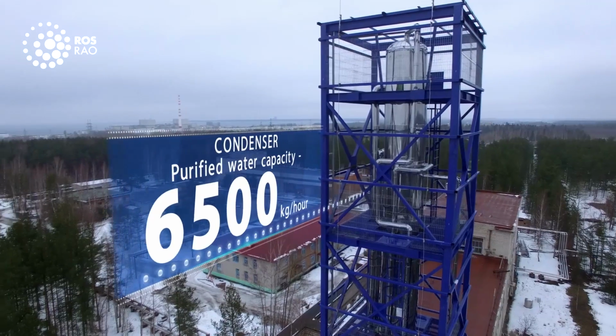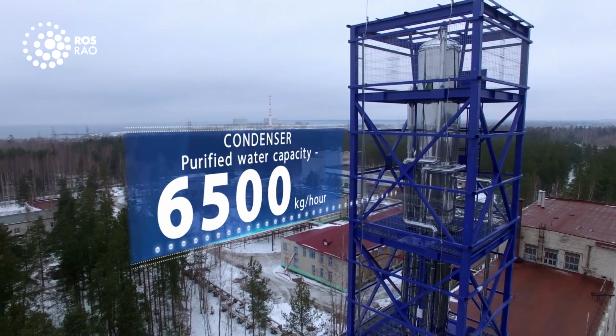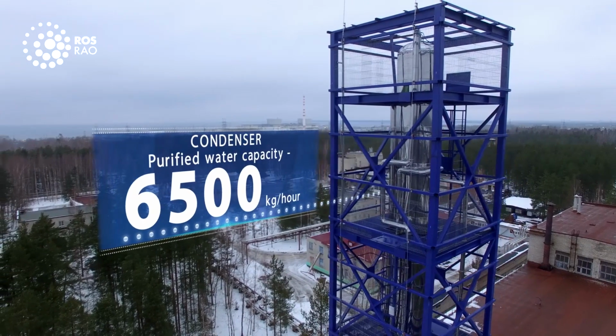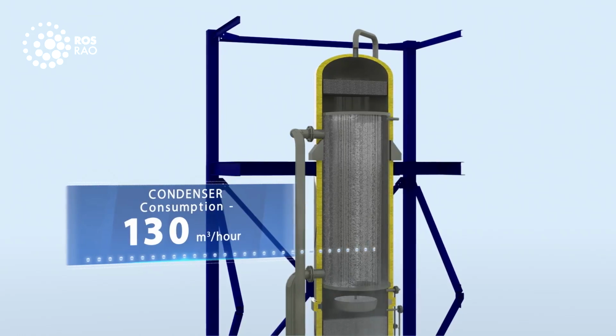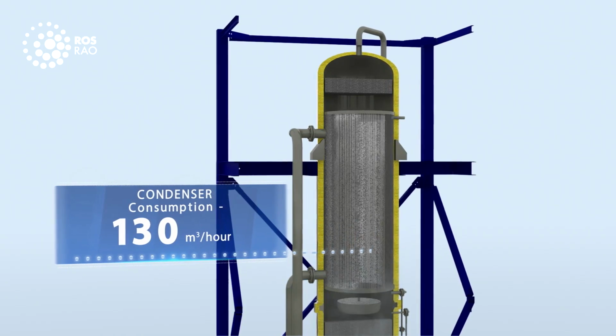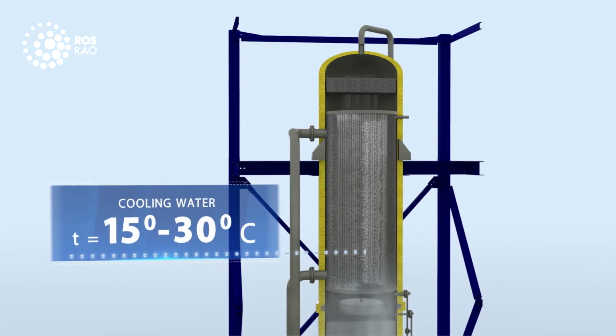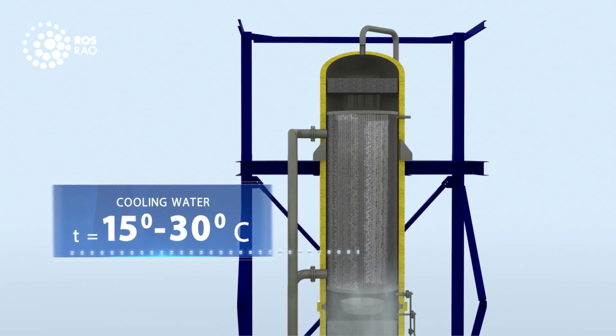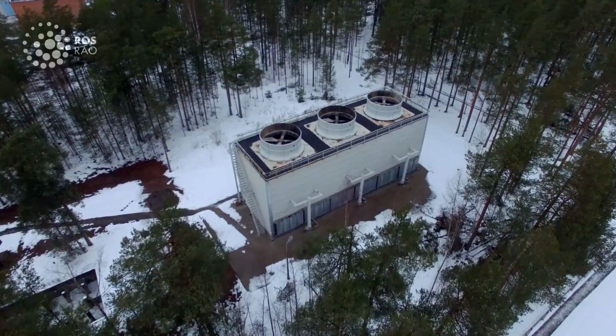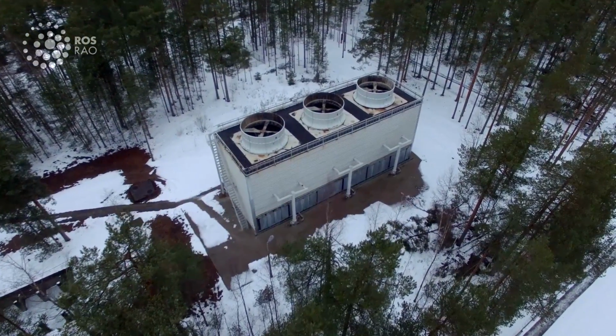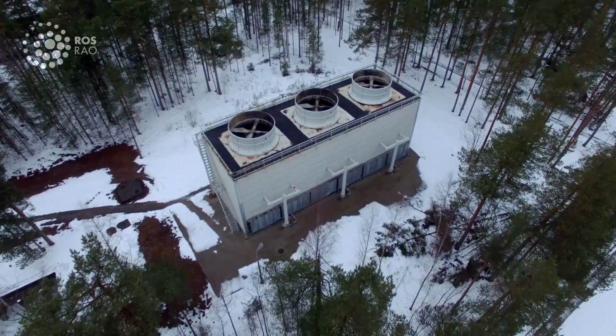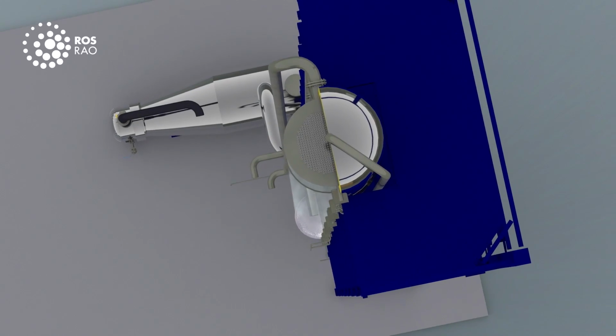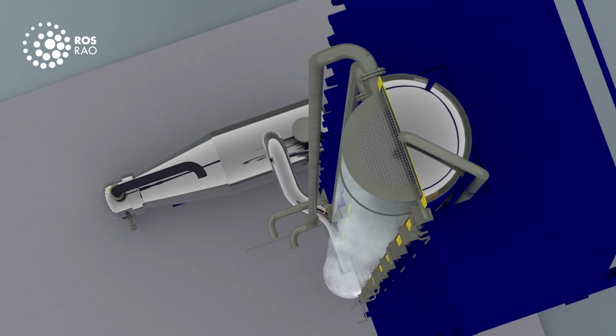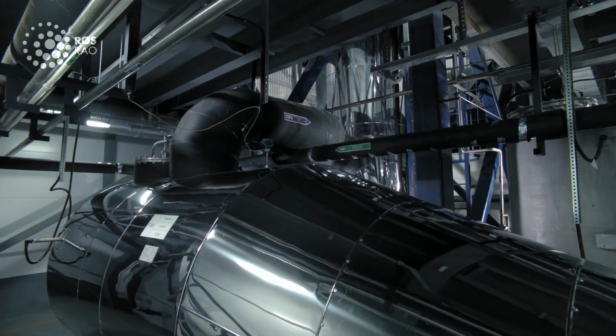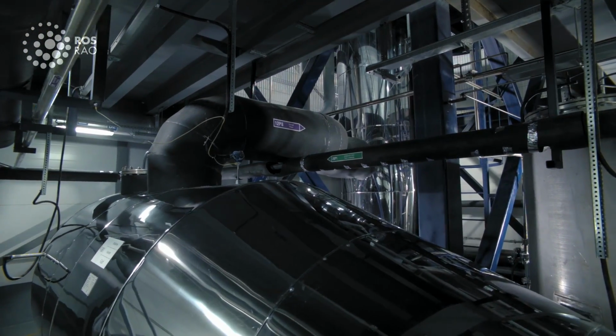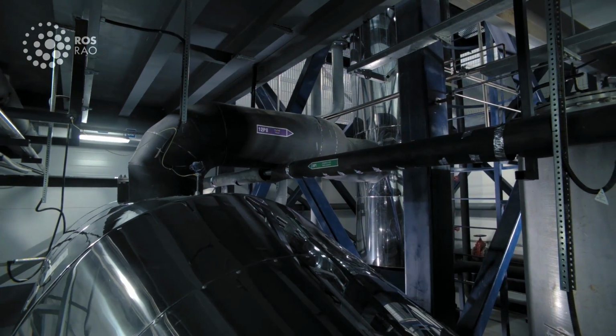The capacity of the condenser installed in the upper part of the column is up to 6,500 kilograms per hour of steam condensate. The condenser is cooled by process water at a flow rate of 130 cubic meters per hour. The cooling water arrives from the cooling towers at RosRAO at a temperature of between 15 and 30 degrees centigrade. Cooling towers are not required for the full-scale unit, since a system with heat recovery from the condenser to the evaporator will be used. The evaporated water arrives for phase isotope exchange from the packing part of the distillation column.